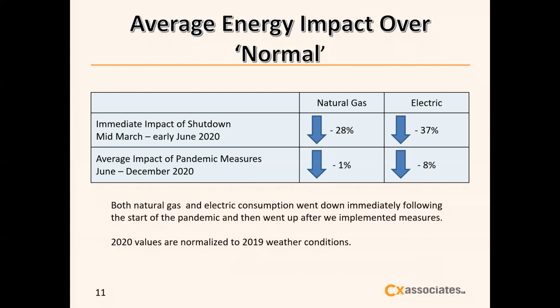The next line on this table shows the impact of operating under the new pandemic normal. This includes not having events and definitely includes smaller lighting and plug load usage, but it also includes increased ventilation and filtration, comfortable space temperatures in more occupied areas, and a limited occupancy of offices, restaurants, and retail. The intent of all this was for a safer operating paradigm meant to sustain businesses through the pandemic.